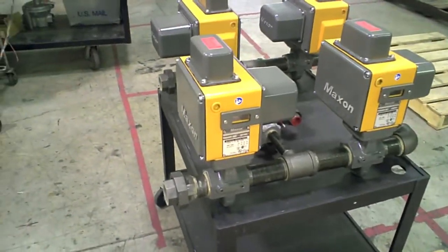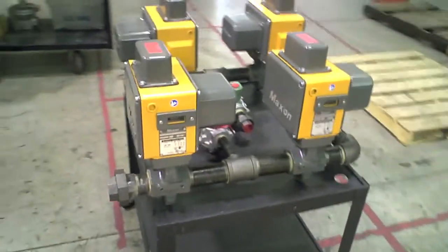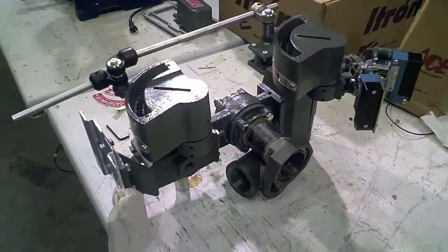Both those devices have Modbus communications for remote start from a central location. We are upgrading both the fuel trains for both gas and oil to Maxon automatic valves and Maxon micro-ratio flow control valves for both the oil and gas.